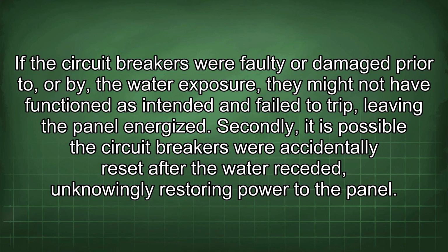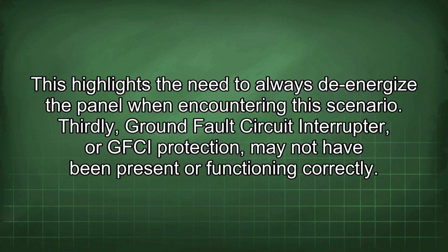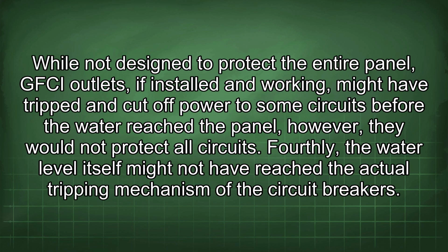Secondly, it is possible the circuit breakers were accidentally reset after the water receded, unknowingly restoring power to the panel. This highlights the need to always de-energize the panel when encountering this scenario. Thirdly, ground fault circuit interrupter, or GFCI protection, may not have been present or functioning correctly. While not designed to protect the entire panel, GFCI outlets, if installed and working, might have tripped and cut off power to some circuits before the water reached the panel. However, they would not protect all circuits.